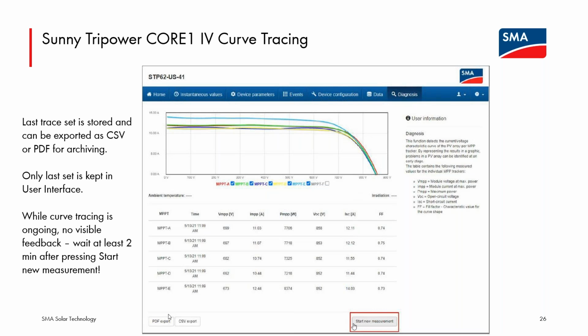When the information is there, you can export the graph as a PDF, or you can export the data itself as a CSV. Only one set, the most recent set of curves, is stored in the user interface of the inverter. So if you want to archive these, to have annual comparisons or 6 month comparisons, whatever you want to do, go ahead and export the data once the new curves appear. Take that, store it. Again, if you have temperature and irradiance measurement for the inverter, those will be displayed.